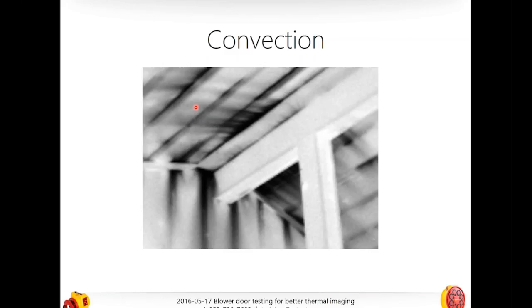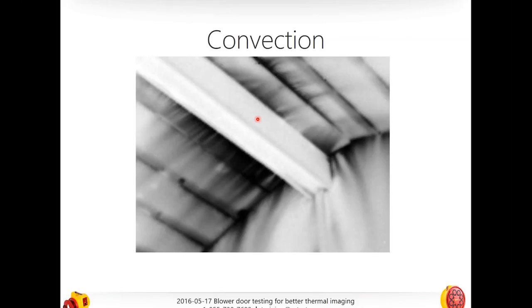Here's another more pronounced line. What is this? — Tongue and groove wood slat on the ceiling and sidewall, with actual cracks moving through. This would not be nearly as obvious — or probably not visible at all — had we not run the blower door. You can also see some seriously exaggerated lines in one area versus another, which indicates really heavy leakage at that specific location.